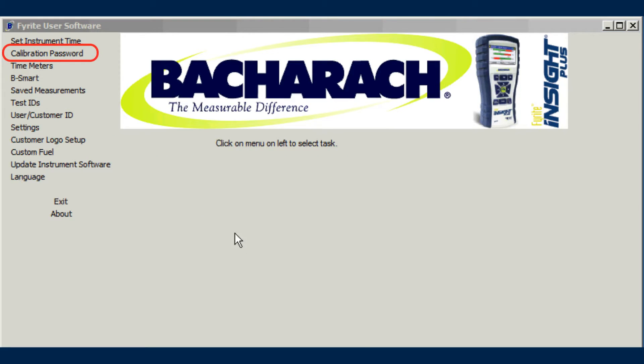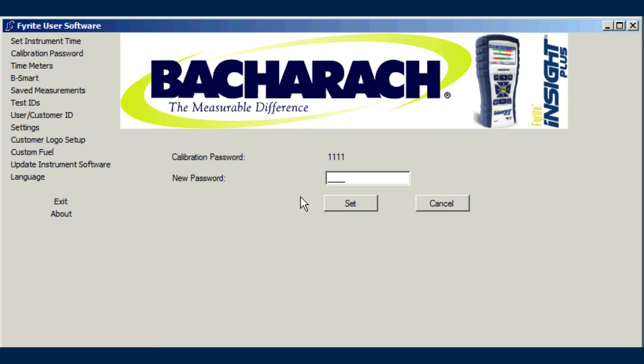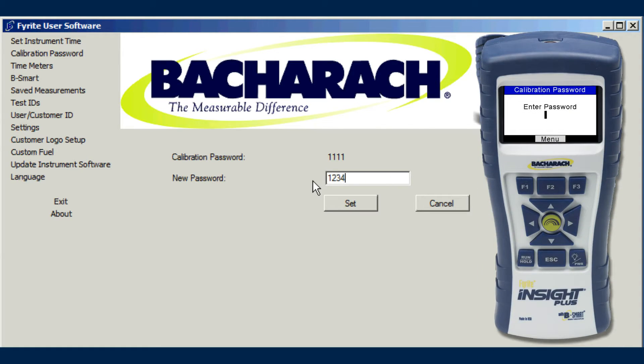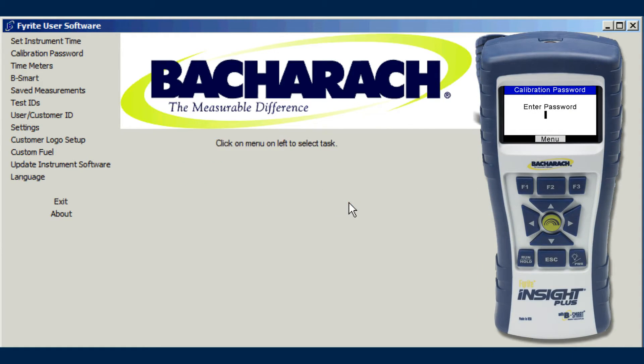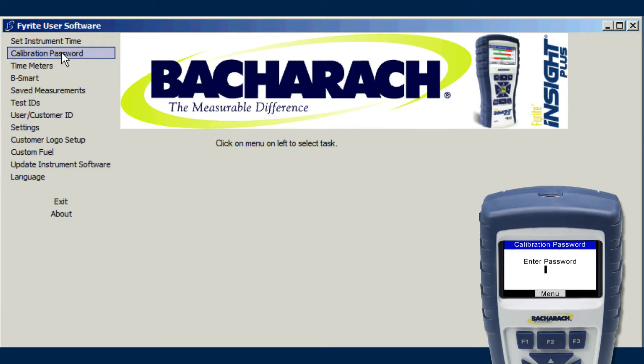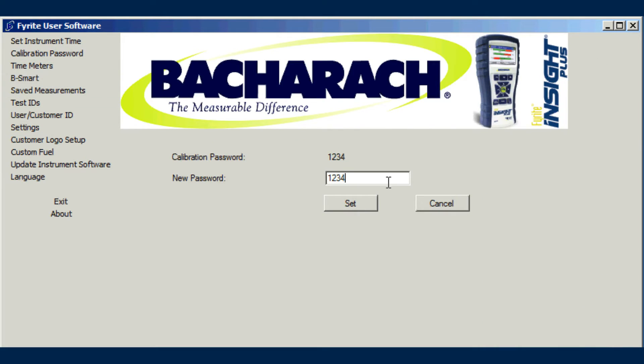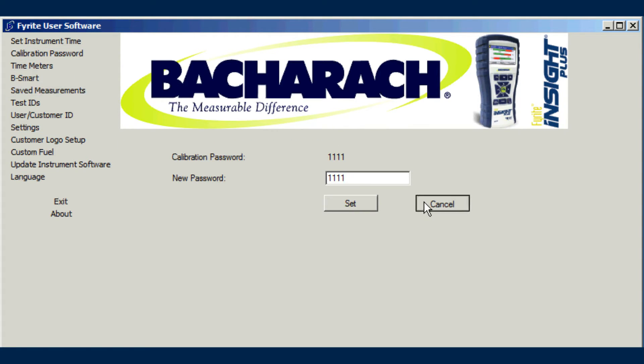Calibration of Bacharach portable analyzers is a very powerful feature that could have unwanted consequences if performed accidentally or incorrectly. For this reason, analyzers require the entry of a password to access the calibration menu. Use the Calibration Password menu item of the FYRITE user software to change this password. The current calibration password is displayed, as is a new password field. Simply type in a new four-digit code and click the Set button. The new password is sent to the instrument.